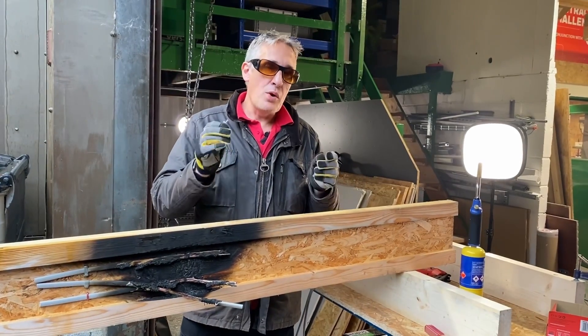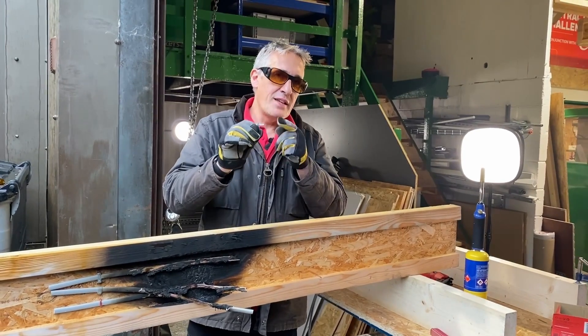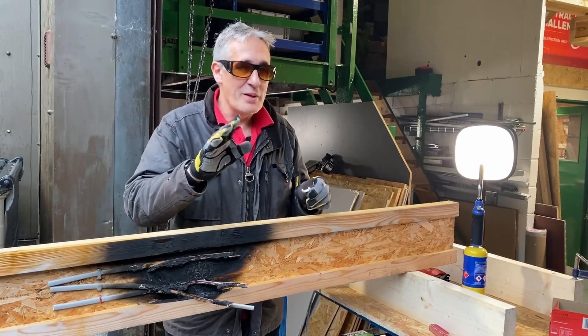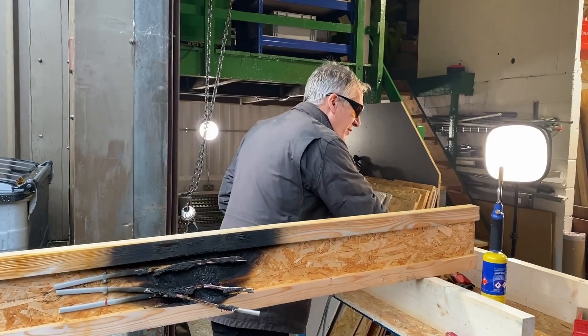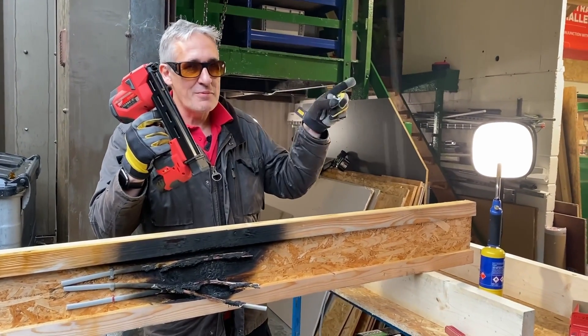I'd say that's pretty conclusive — the Milwaukee clips perform equally, if not better, than this fire-rated clip that people may be used to using. However, don't rely on this video in a court of law, because the eFix Fire Performance Test Centre isn't validated to give certificates. But if you haven't seen the review of this tool that puts the clips in, check it out — it's over here.